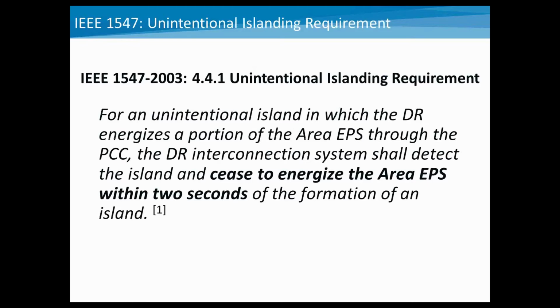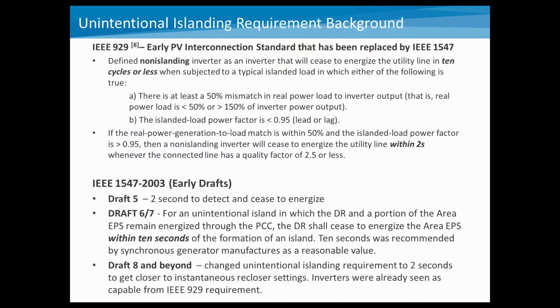So moving on to specific requirements around unintentional islanding. IEEE 1547, section 4.4.1 gives the unintentional islanding requirement. And it's stated here: for an unintentional island in which the DR energizes a portion of the area EPS through the PCC, the DR interconnection system shall detect the island and cease to energize the area EPS within 2 seconds of the formation of the island. So the key point here is realizing that it needs to detect and cease to energize within 2 seconds per the requirement.